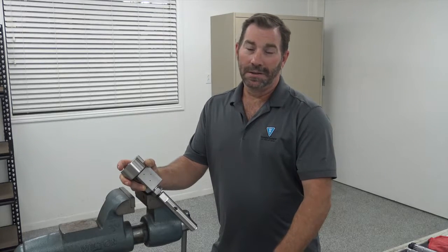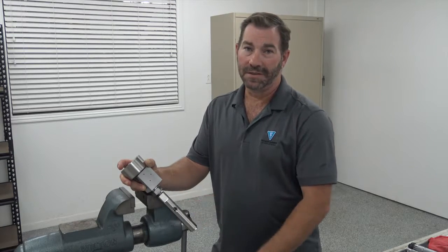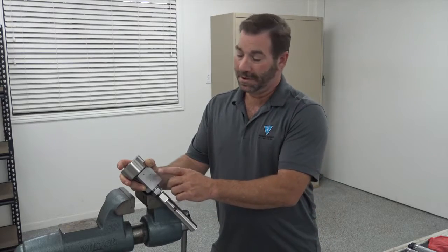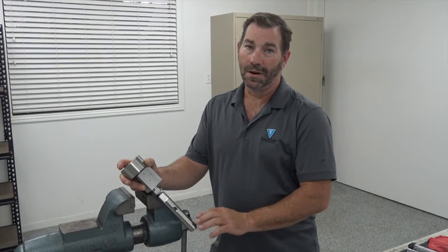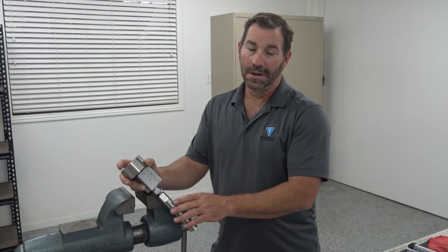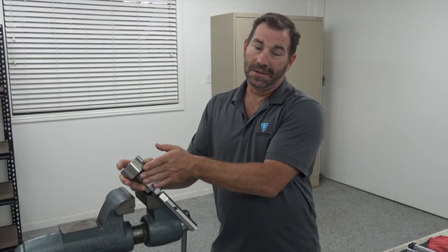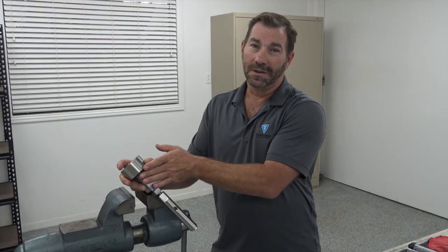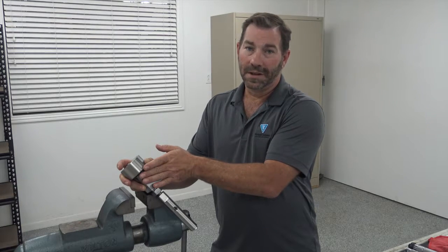Welcome back. Today's video I'm going to walk you through the repair procedure for a normally open K-series pneumatic valve assembly. This particular valve is a normally open valve and it's got a catcher tube on the bottom of it, which actually makes it a dump valve assembly as well. Anytime you're working on the valve assembly from here up, it's the same whether you're using it for a cutting valve, a valve in a block and bleed, or things like that. It's all the same valve mechanism.